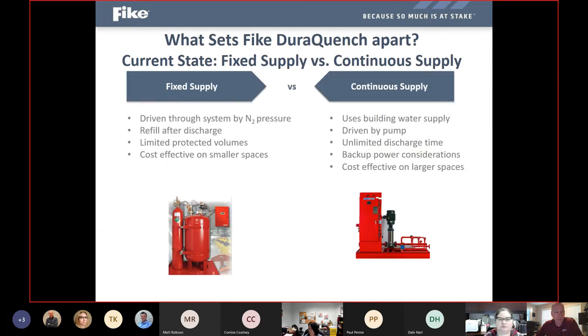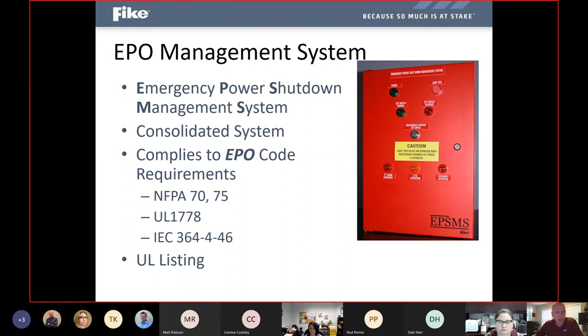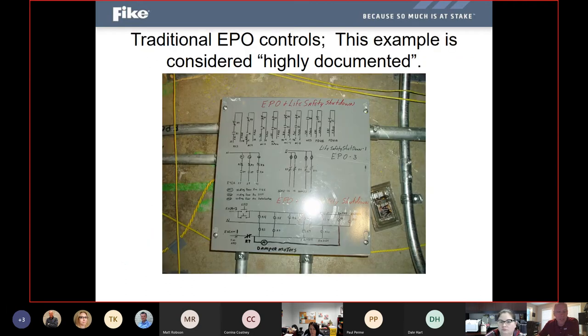We'll skip over some of these slides in recognition of time. One of the other products I wanted to touch on that Fike has available is an EPO, or emergency power shutdown management system, that we market as our EPSMS systems. In a lot of cases, especially in your mission critical facilities, power shutdown in a fire event is very important because you want to remove that source of the electrical feed to the equipment that may have triggered your activation. And a lot of times the EPO wiring, which is obviously extremely critical for those areas, is not very documented.